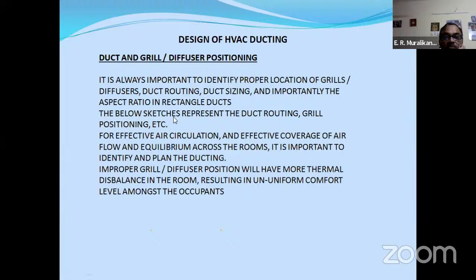Now we show the duct routing and grill positioning. For effective air circulation, effective coverage of air, and flow and equilibrium across the rooms, it is important to identify and plan the ducting. Improper grill and diffuser position will cause more thermal imbalance in the room, resulting in non-uniform comfort level amongst the occupants. Now, these are the three options. This is a room, this is the shaded or supply grill, this is the unshaded or return air grill.